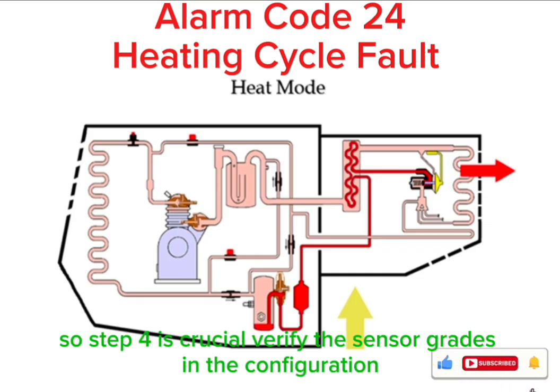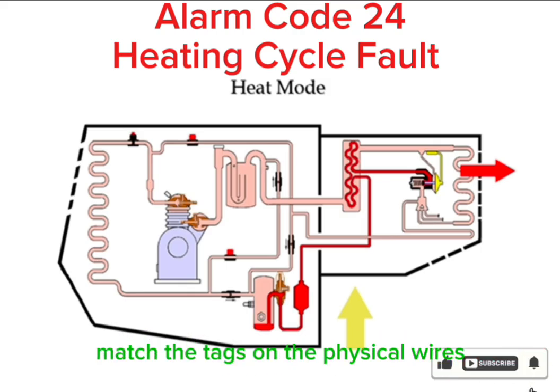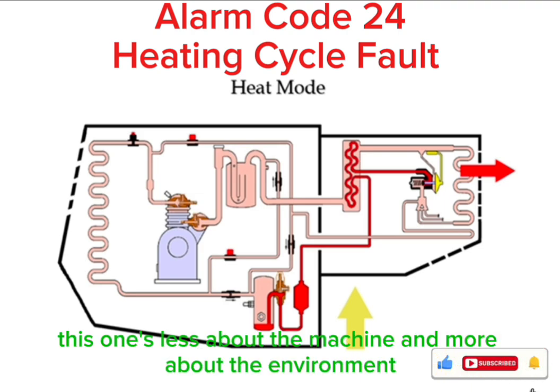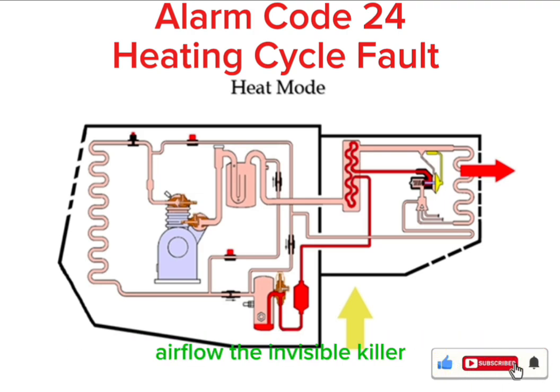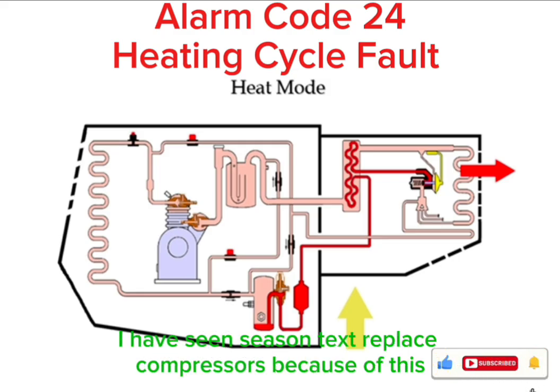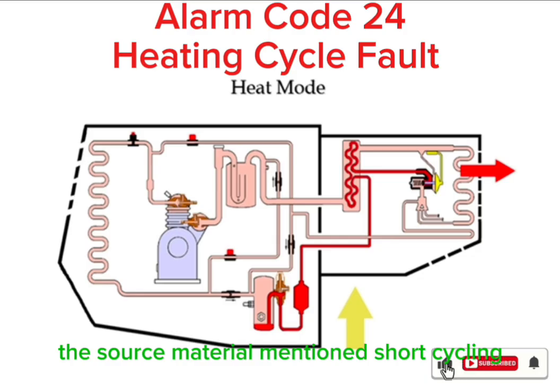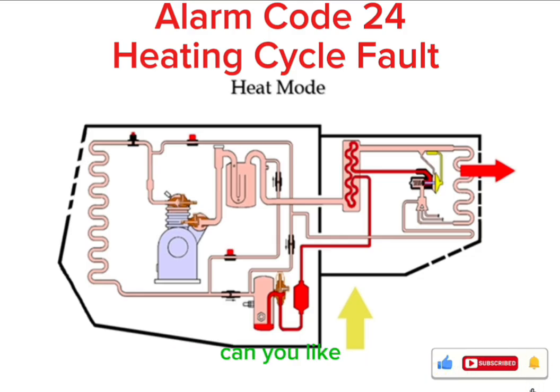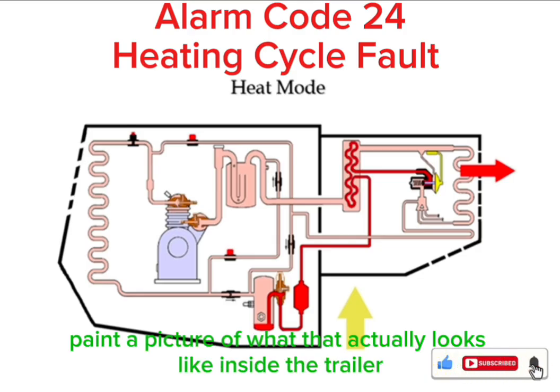Exactly. So step 4 is crucial. Verify the sensor grades in the configuration match the tags on the physical wires. Don't assume. Look. Okay, moving on. Step 5. This one's less about the machine and more about the environment. Airflow. The invisible killer. I have seen seasoned techs replace compressors because of this. The source material mentions short cycling. Can you paint a picture of what that actually looks like inside the trailer?